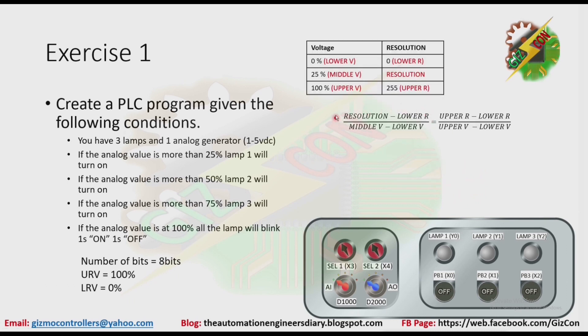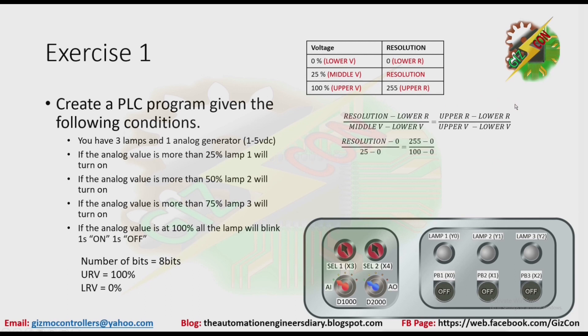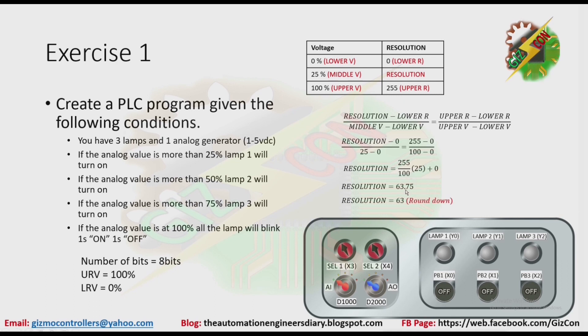Next we need to find the equivalent resolution given the value of the voltage. If we have 0%, we have our resolution of 0. If we have 100%, we have the upper range value of 255. But from our computation, we have 256 — but now we have 255. Why is that? Because including 0, we have 256 values. Now we are looking for the equivalent resolution at 25% voltage. Using algebra, we can have our resolution of 63.75, but resolution doesn't have any decimal place, so we need to round it down.